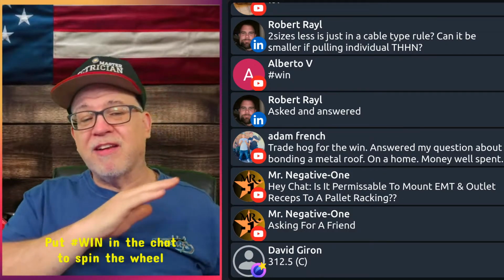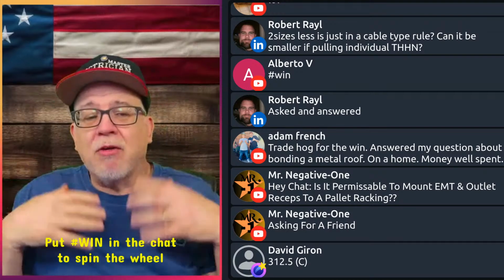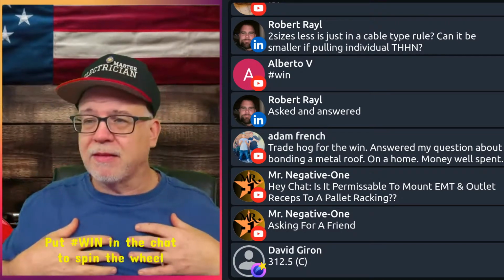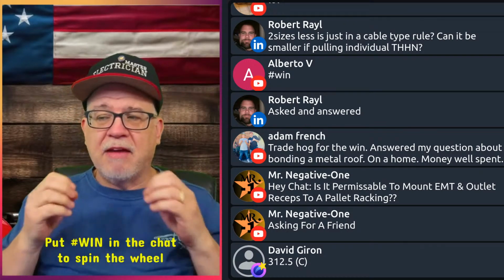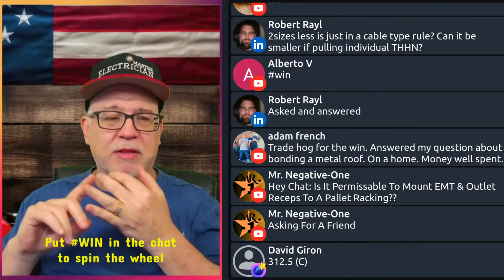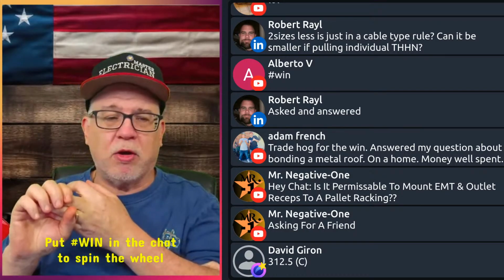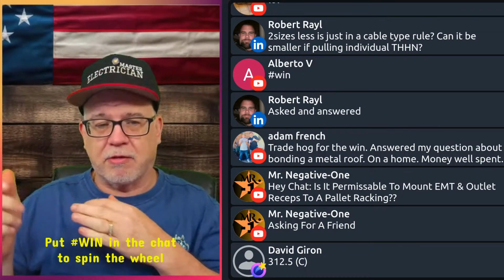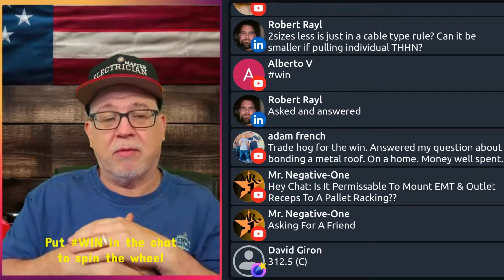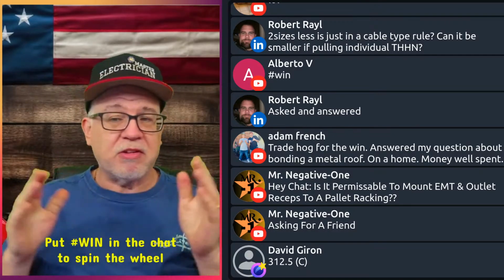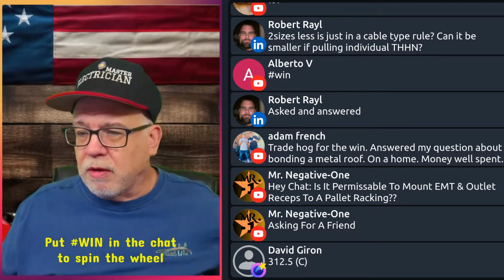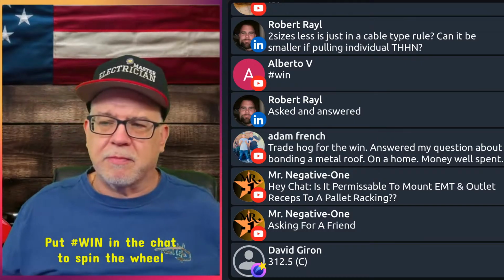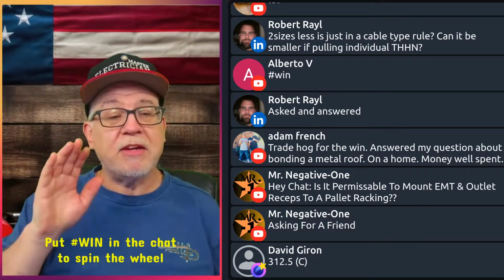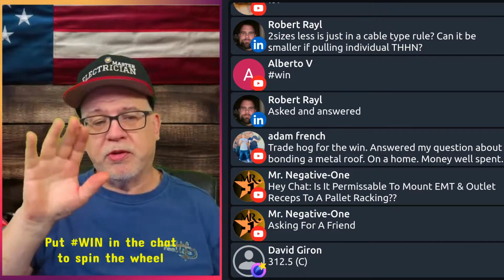Now, as far as cleaning off the enamel, I don't have a problem with the enamel part, the coating. I have a problem with the bus bars. I have a problem with the lugging. I have a problem with if you get spray on the breakers and it could affect their operation. Hell, if I know what's in the cleaner that you're using, much less what you spray on it. So I think it's the electrician's responsibility to make sure that you put your covers in there.